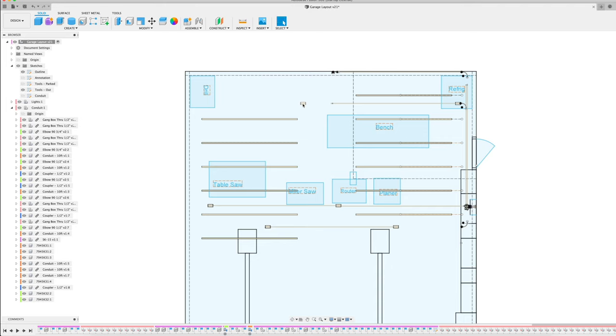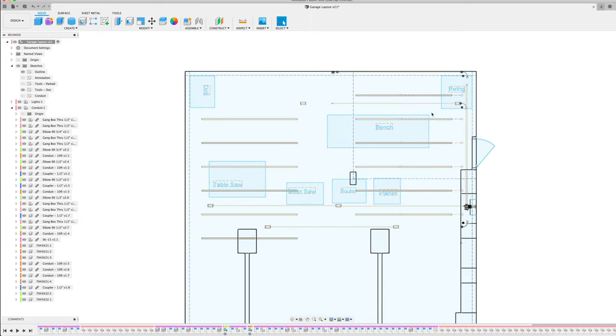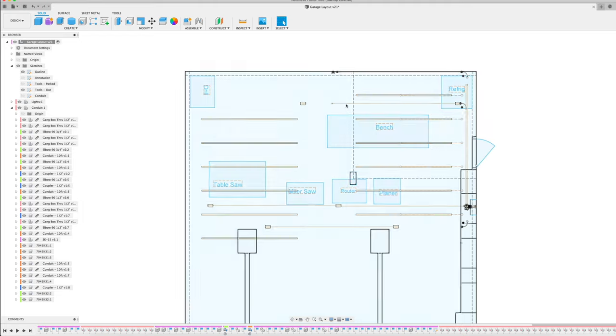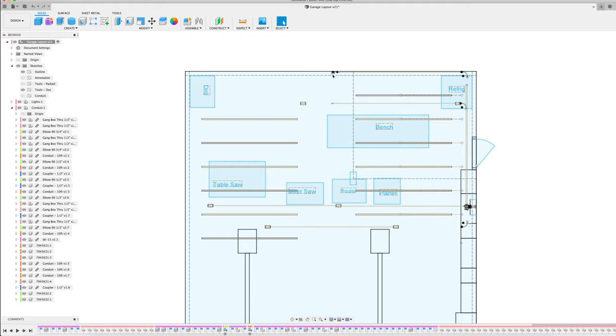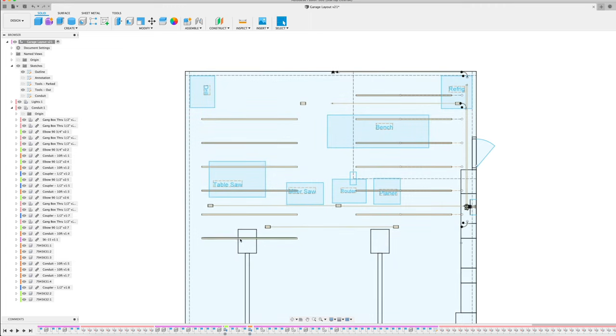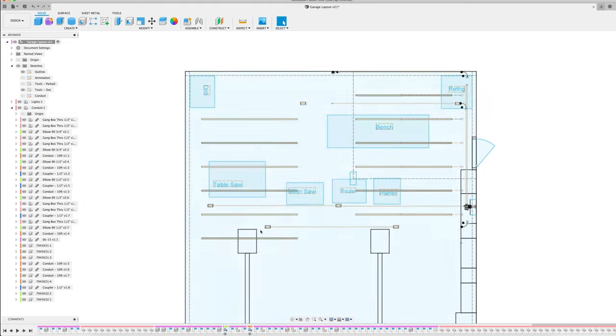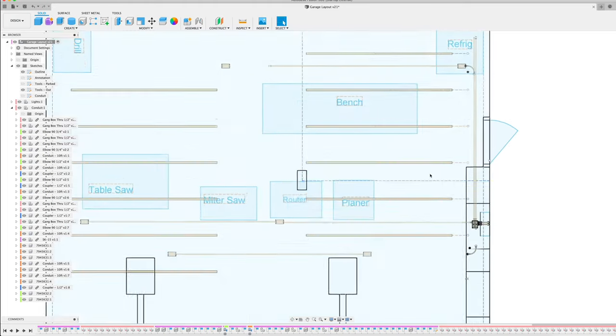I have two receptacles here and here for the lights. These are actually on a switch, two independent switches, one for the right-hand side of the garage and one for the left-hand side. I also added a power receptacle right here for the vacuum system for the dust collector. I wanted that on its own circuit because it draws a lot of power, about 12 amps or so. Everything's a 20 amp circuit except for the garage door openers which are on a 15 amp circuit because they don't draw very much power and they're never really running at exactly the same time. That was the original plan.